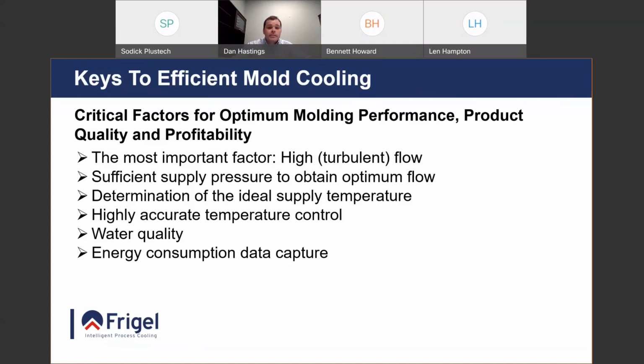Determination of the ideal temperature. What is your temperature set point going to be? Does it make sense for the particular application, the typical material you're running? Highly accurate temperature control. If you have a temperature control unit, are we using a solenoid valve that's open-close, and it's very difficult to maintain constant temperature when it's all or nothing? Or do we have a modulating valve where we can dose the cooling water to maintain a temperature within, say, 1-2 degrees Fahrenheit?